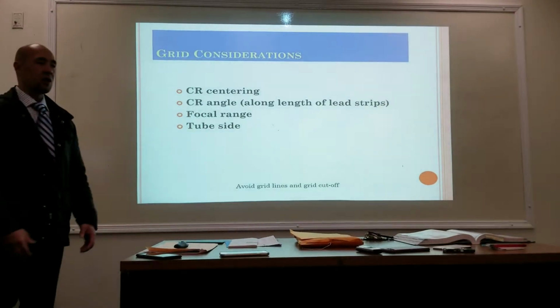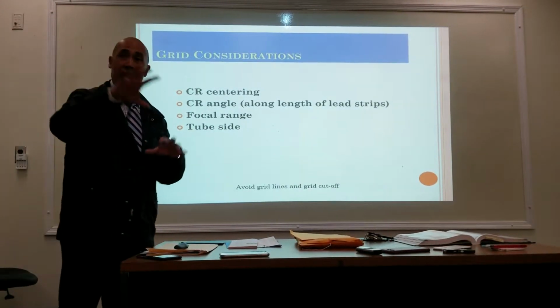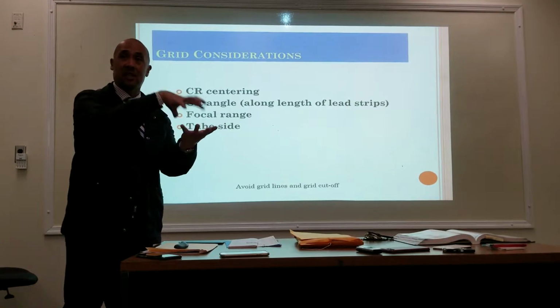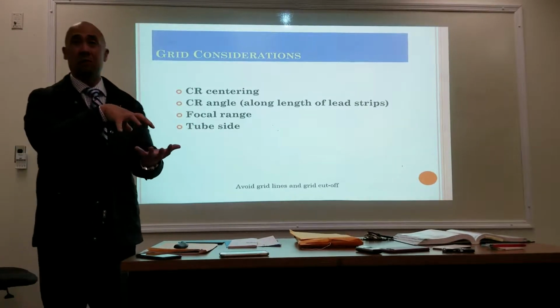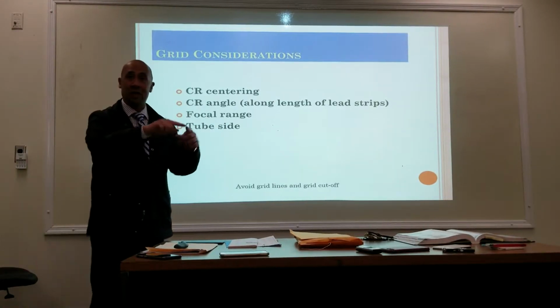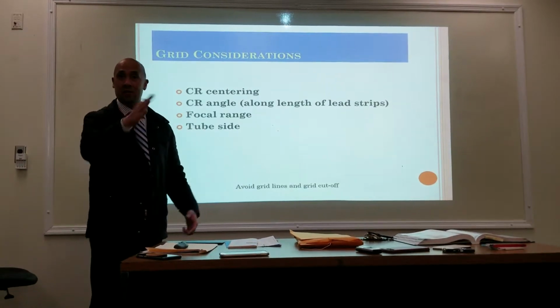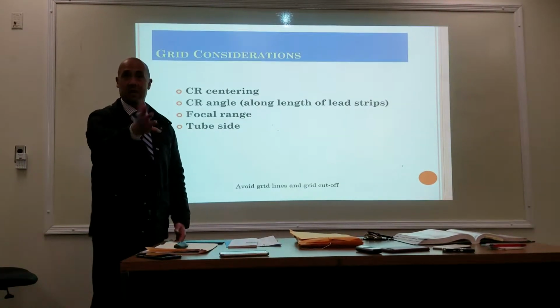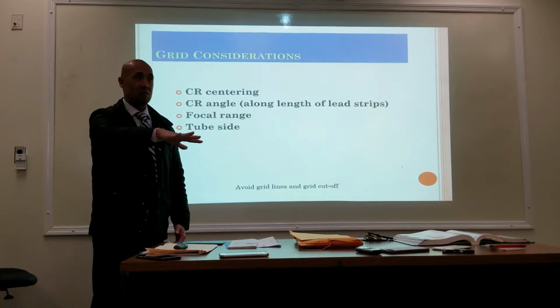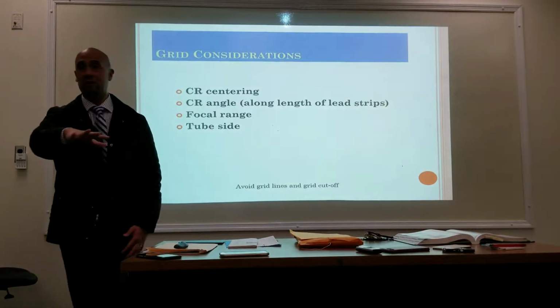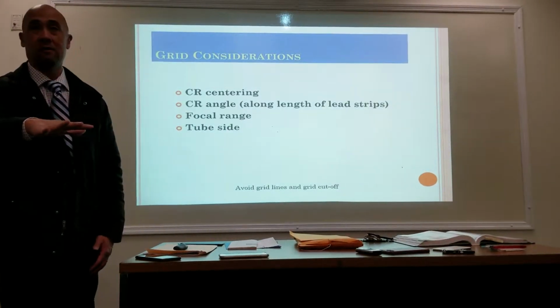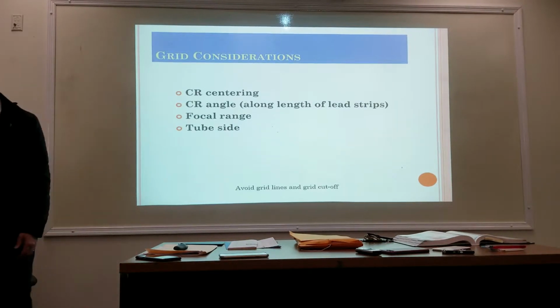And some grids are completely flat. We've had grids that have a cap or an edge to it that fits nicely over the image receptor. But there are some grids that are completely flat without a lip around them. So you have to make sure you're using the correct side. If it's upside down, not placed correctly over your image receptor, you can get grid cutoff. Okay?